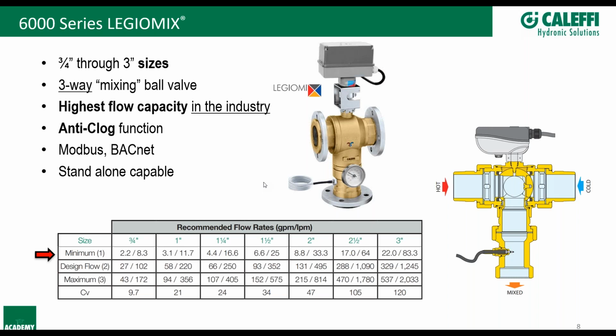Great question. The control can definitely be remote mounted, hundreds of feet away if necessary. I've seen it where the control is in the building engineer's office and the valve is in the mechanical room, to prevent tinkering. The actuator on the LegioMix is a 24-volt floating actuator, so it's a standard 24-volt control signal, no problem extending wires. All the sensors are 10K ohm sensors, so adding a couple hundred feet of 18 gauge wire changes the temperature reading slightly due to extra resistance, but it's so minimal you won't notice a difference.